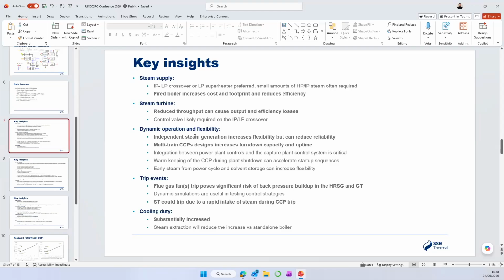Looking at, again, I suppose, trips and reliability, most of the FEED studies cited the flue gas fan as a significant reliability and trip and hazard during a trip event, because if your flue gas fan trips, you very possibly will get a pressure buildup in your HRSG and back pressure on your GT that could lead to damage. So there has to be some capacity or some way to release that pressure very, very quickly once a fan trips. So fast acting dampers in your bypass stack is a common approach.